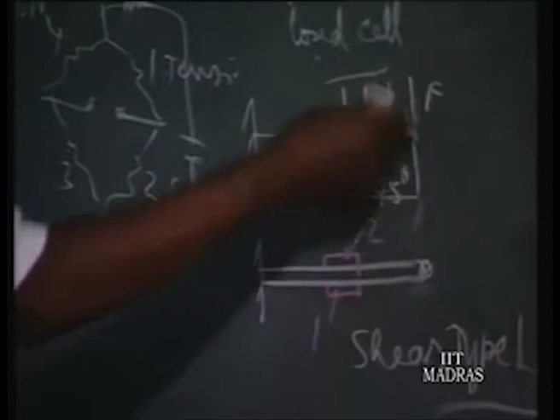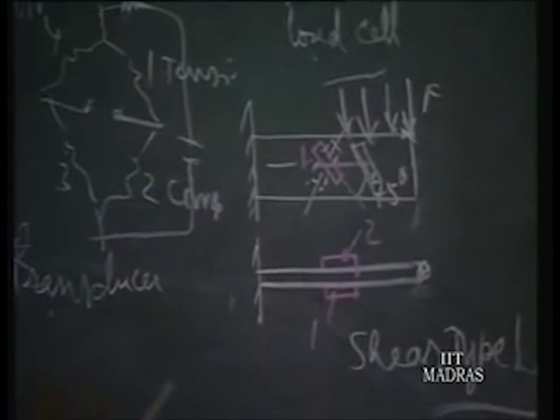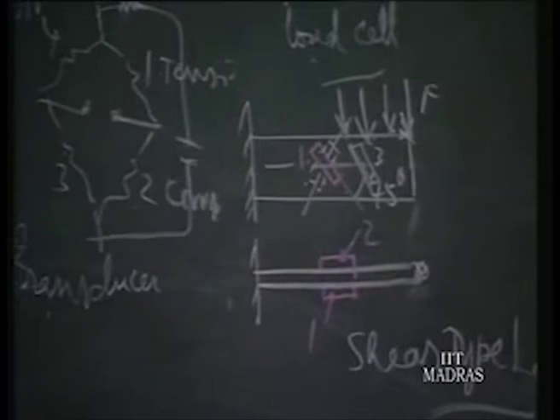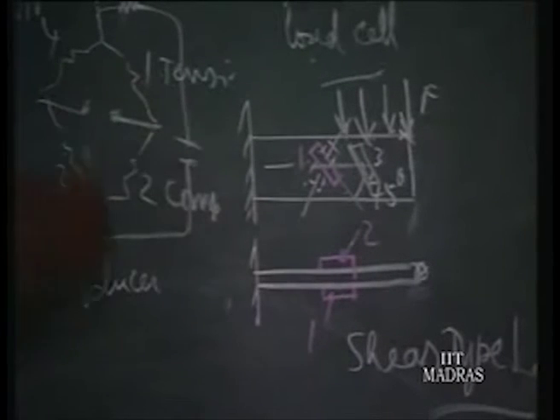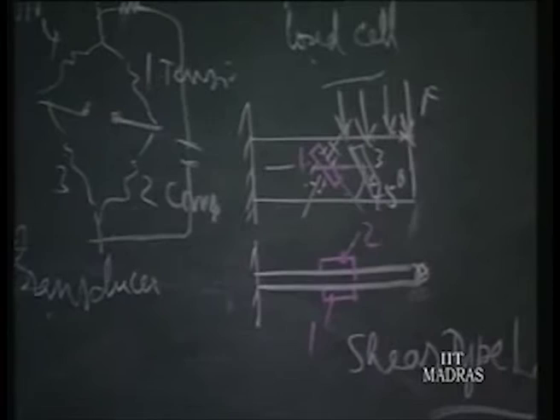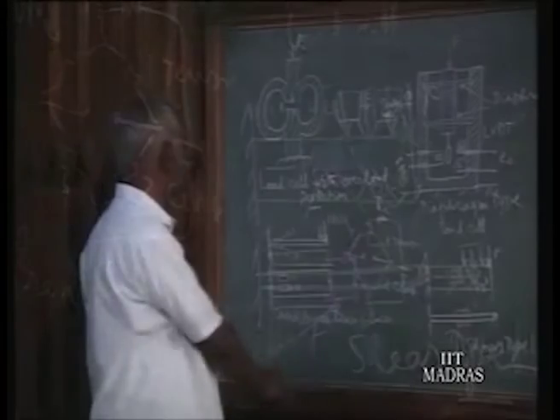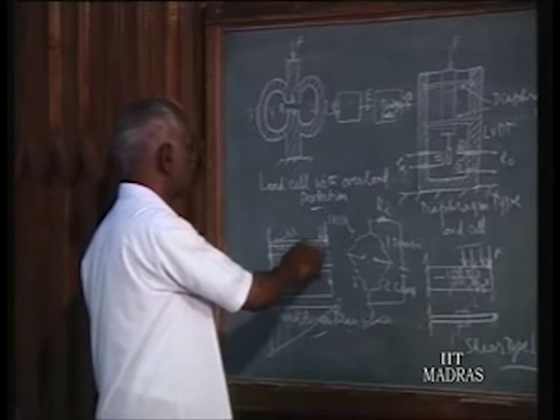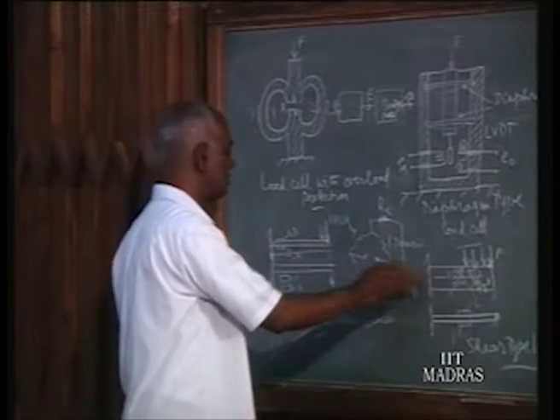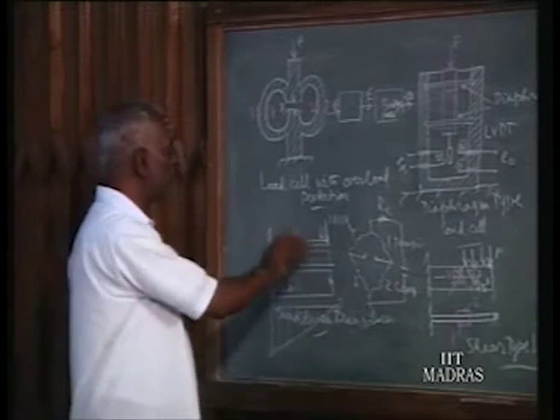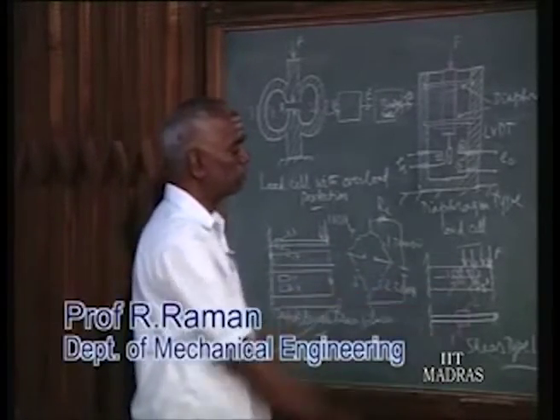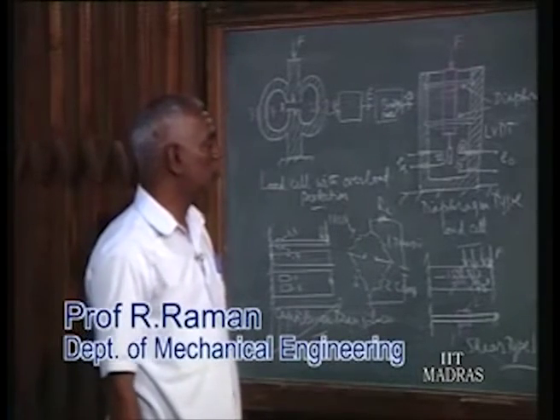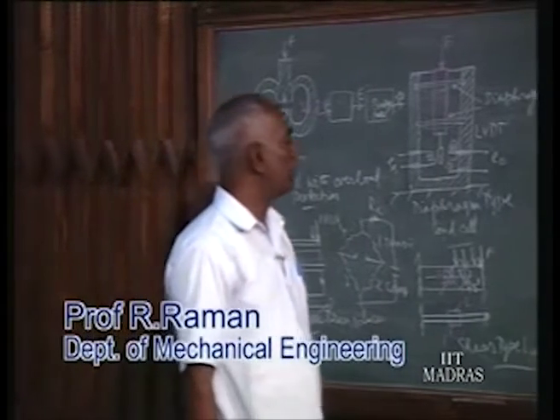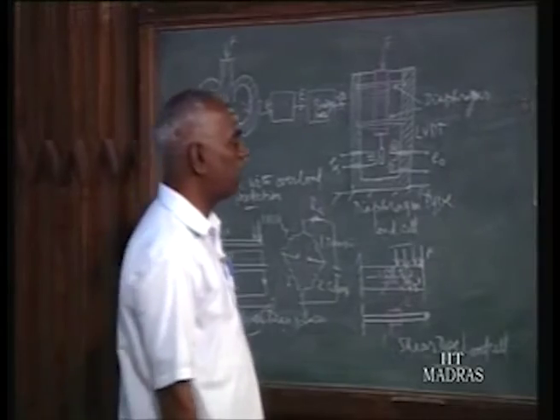In the same way you can have another parallel, and you can have 4 strain gauges also. This will be 3. Behind that, at 90 degrees to that, it will be 4. So that is a full bridge. If 1 and 2 alone, then we are making use of a half bridge. So that problem of loading at an exact place is removed, and this instrumentation is not sensitive to the loading point. So it is nowadays very often used. Shear type load cell is often used. And the next thing we are going to see is the 3-dimensional load cell.